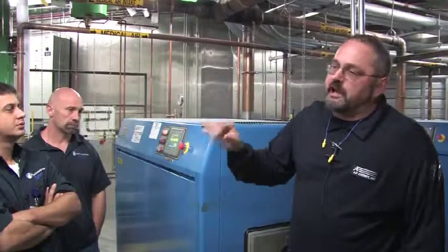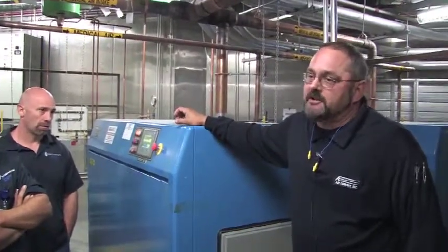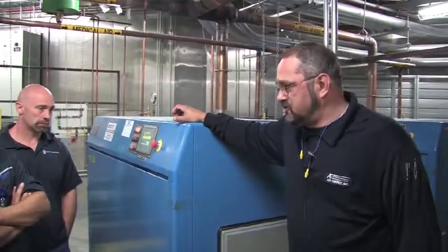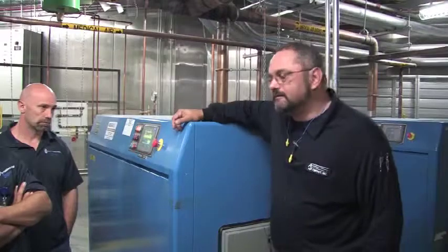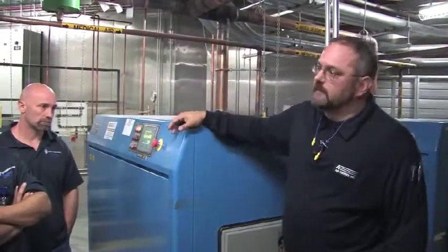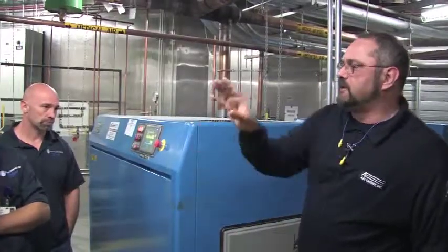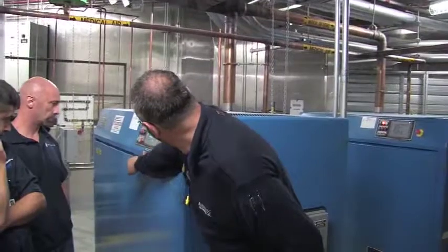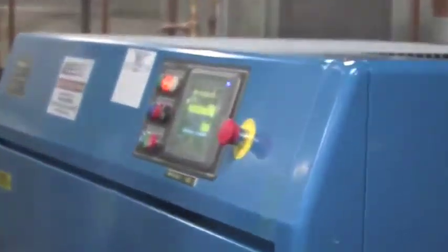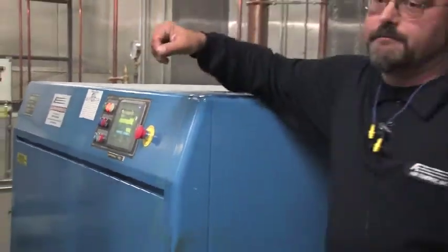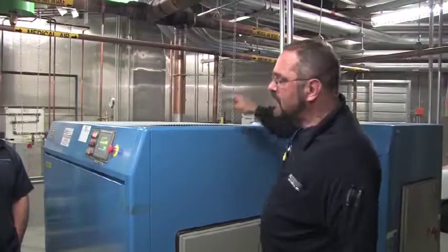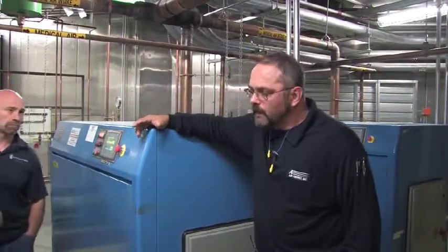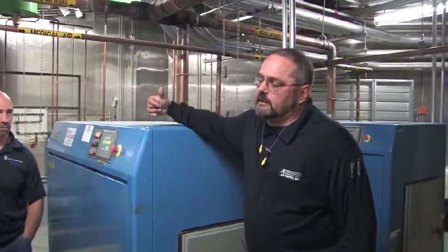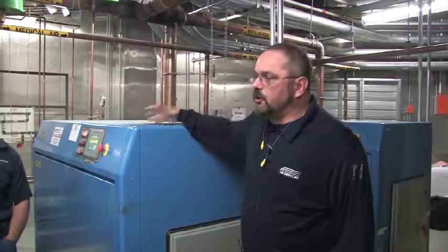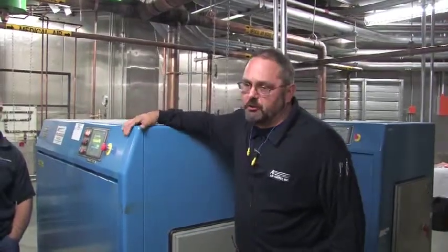With 3 machines, the scenario gets a little different. The way this setup works is you have a master machine and 2 slave machines. So the master machine is number 1. So the front of that one will say it's the master and it's node 1. If you look at these, they'll say compressor 2, node 2. So compressor 1, compressor 2, compressor 3, and they're actually set up consistently node 1, node 2, node 3 as far as the sequencing is concerned. The biggest difference is that in the internal programming, node 2 and node 3 are looking over to node 1 to tell them what to do.